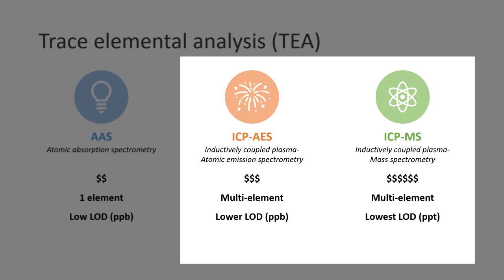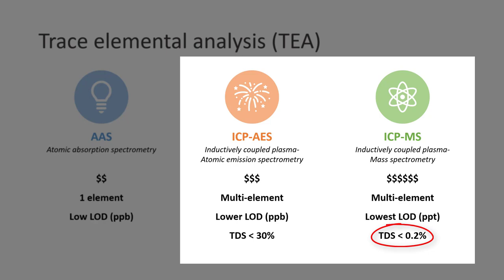So which one shall we choose? There is another practical consideration: the amount of total dissolved solid, or TDS. In general, ICP-AES has a higher tolerance for TDS, up to 30% depending on the instrument and accessories used. On the other hand, ICP-MS has a lower tolerance for TDS, lower than 0.2%. Therefore, sample dilution is often necessary for ICP-MS analysis. In this e-lecture series, we are going to focus on ICP-AES.